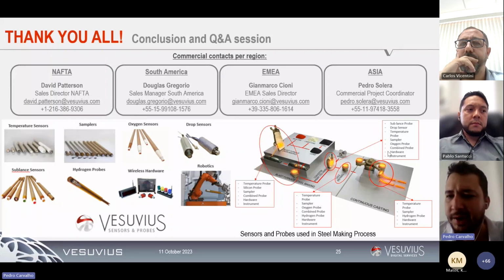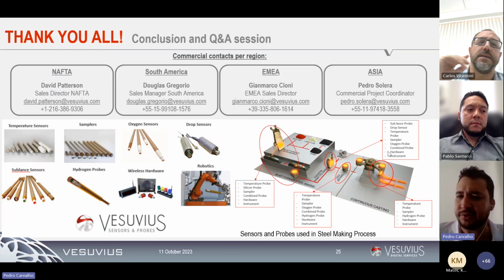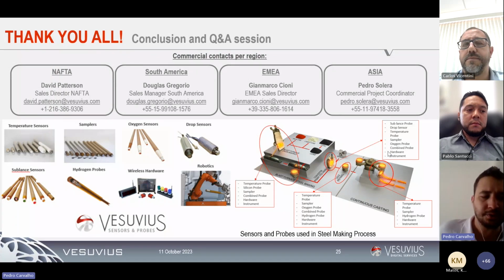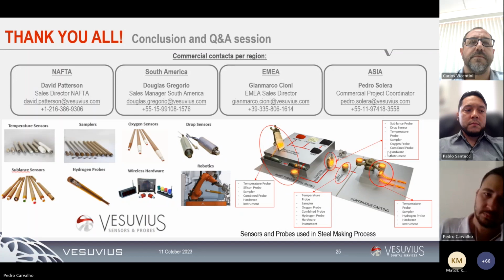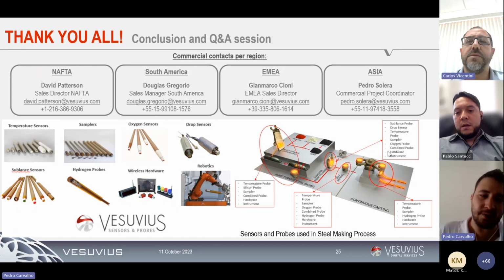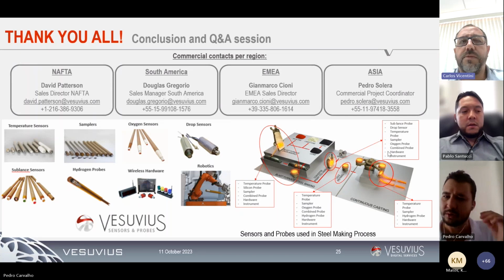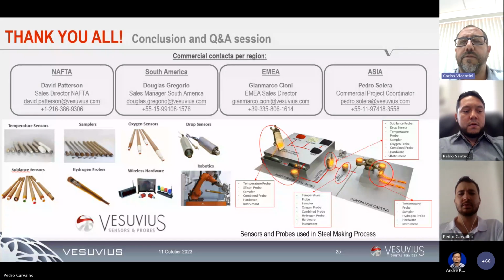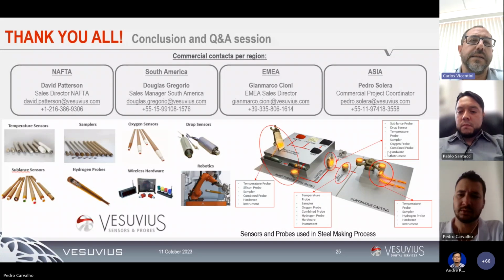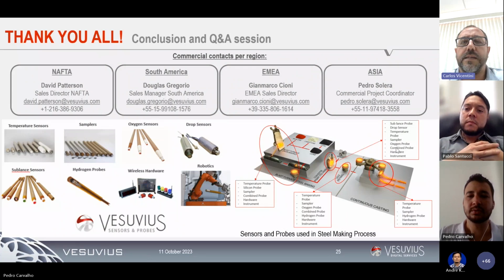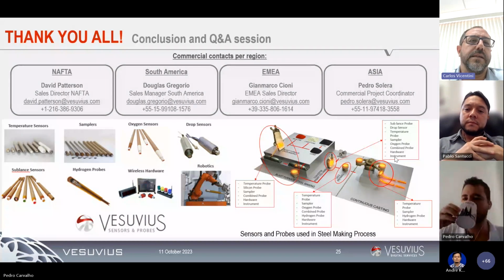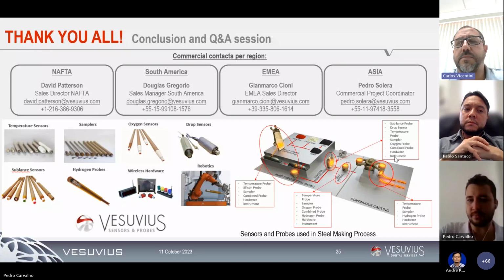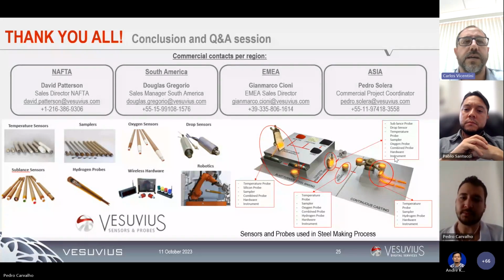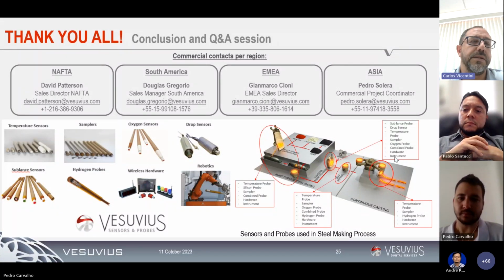Can an N2 line be used with the Vesuvius instrument or just a nitrogen bottle? I think about the calibration. Yeah. We really recommend using the bottle. In fact, the bottle or line gas is not a big problem. The question is the purity. To take good measurements in terms of hydrogen, it's very important to use a high purity nitrogen as the base of the measurement.